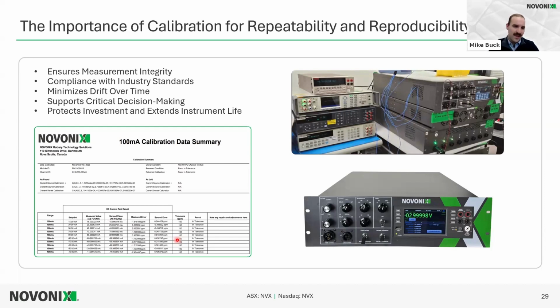And this helps customers at the end of the day because it makes them able to trust the instrument more than the competitors, and it makes it a very, very good instrument to run for a lot of years. Calibration is a very important process because we've seen from competition methods that use functions within multimeters, like the current shunt internal to the multimeter, if you check the specification sheet of those devices, it doesn't exactly match a high precision output.